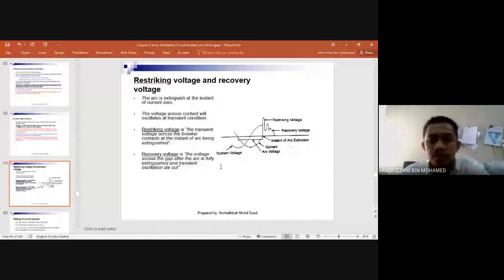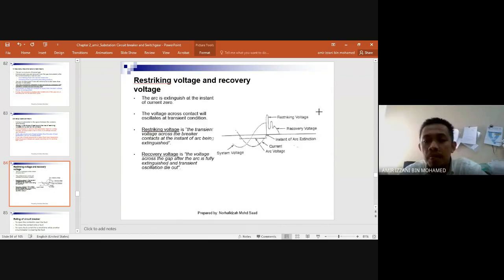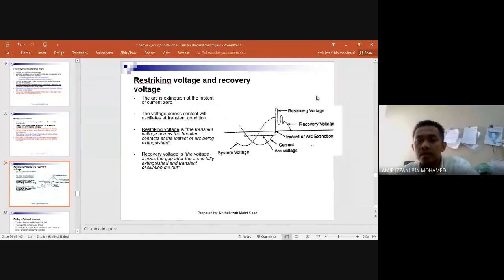Okay, now let's take a look at restriking voltage. The arc is extinguished at the instant of current zero. The voltage across the contact will oscillate as a transient condition. The restriking voltage is the transient voltage across the breaker contact at the instant of the arc being extinguished. So you can see from this figure, this is the restriking voltage if the second cycle of the arc is to occur again. And the recovery voltage is the voltage across the gap after the arc is fully extinguished and transient oscillations disappear. So at this recovery voltage, no more arcing.